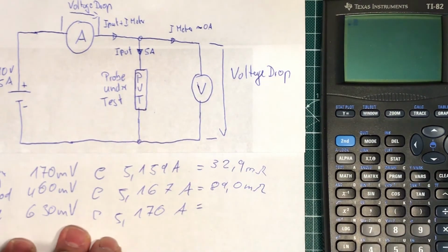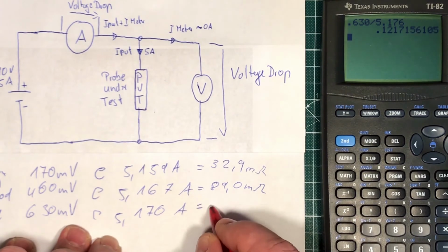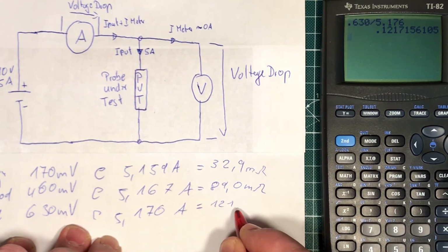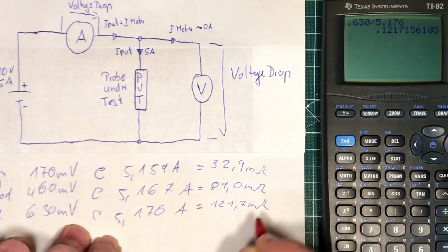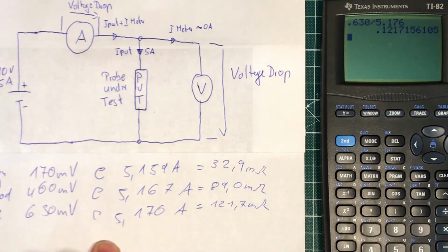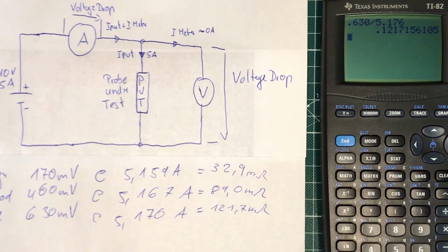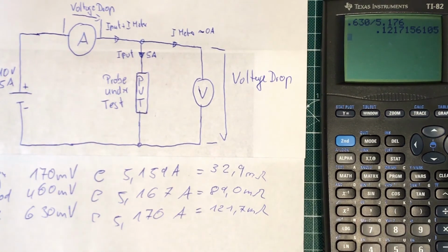And now to the worst one: 0.63 - yeah there's a point, okay, I didn't have the 0 - divided by 5.176 amps is about 121 milliohm. That is a really high resistance cable.